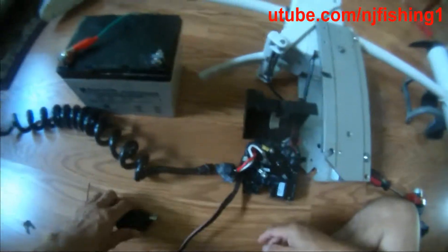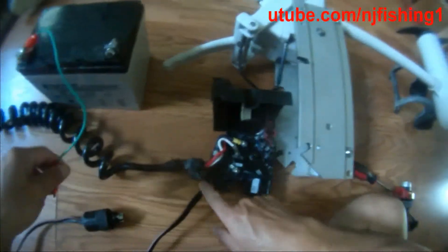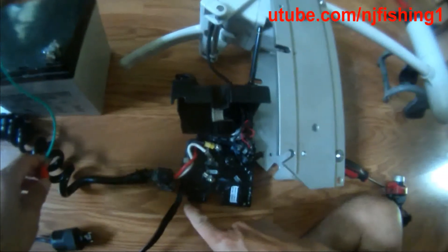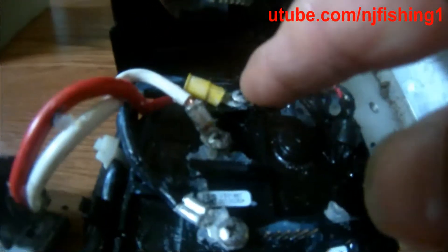I'm going to see if I have power here and here. This is the power line that feeds in. This wire is going in the outer bottom and then comes to this yellow block here. This is the positive. The negative is this top wire that my finger is touching — it travels and follows through here. This is the negative. I'm going to put my voltage meter — positive here, negative here — and try to see if I get any voltage.